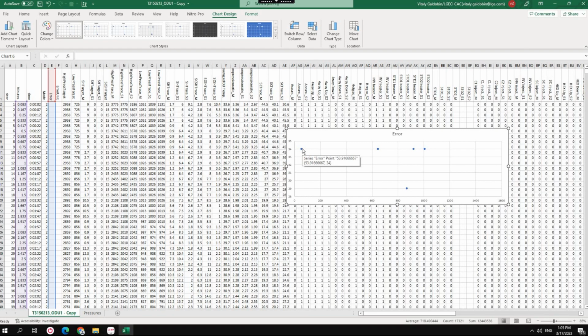If you point your mouse at the chart graph, it will show you the value. First, CH34 happened after 60 minutes from the beginning of the recording. Then again CH34 and CH29. CH29 is compressor overcurrent. Now let's make a chart for current values and narrow it down to when the error happened.